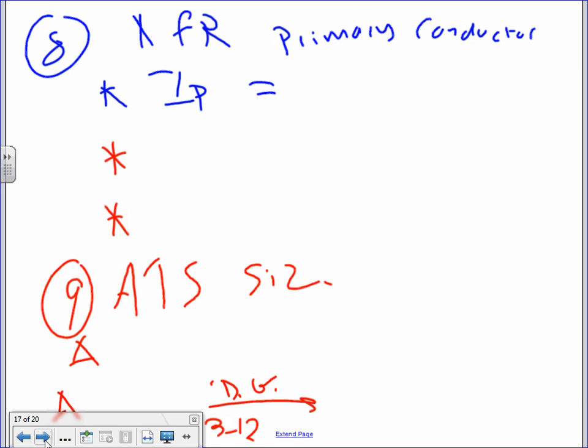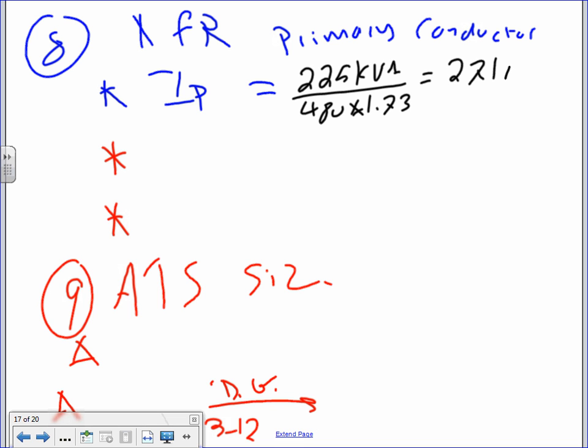Okay, next, now we need the transformer primary conductor. The transformer primary conductor, that will be number 8. You need to find the conductors. Take your transformer, which is 225K, divided by the primary, which is 480 times 1.73. And when you do your math, you're going to end up with 271 amp. That's the primary conductor, okay? 271 amp.